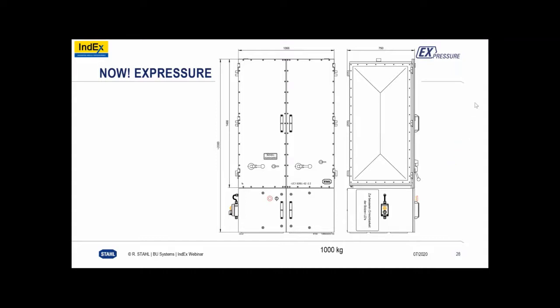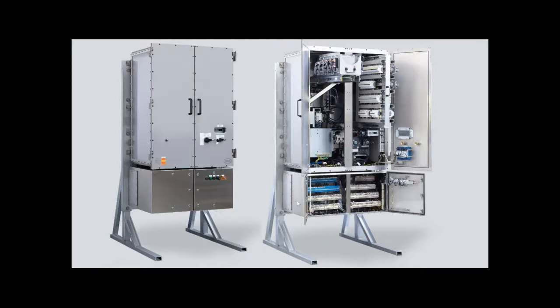Okay, if you go one slide further, yeah. Sure. Also, somebody was asking, can an empty enclosure be sold? Yes, but we are thinking of solutions together, because this is always the question: are you certified to make an assembly? Because what are you doing with an empty enclosure? This solution, what you are seeing now on the slide, is a complete certified and engineered solution from us, from R.Stahl, and it is certified as an assembly with our rating plate. If you are buying an empty enclosure, you have an empty enclosure, but you are not allowed to install anything inside of the cabinet. You have to go to a certified body and test laboratory to certify it as an assembly, and you are then the manufacturer for this combination.